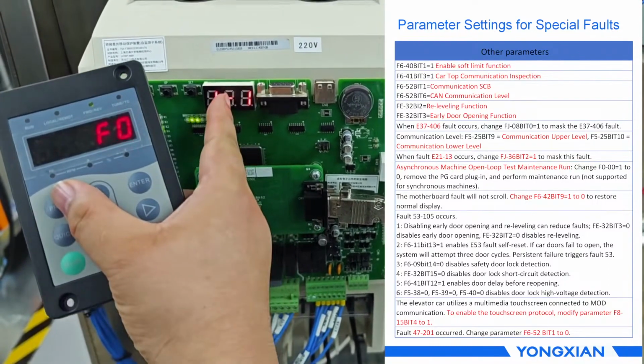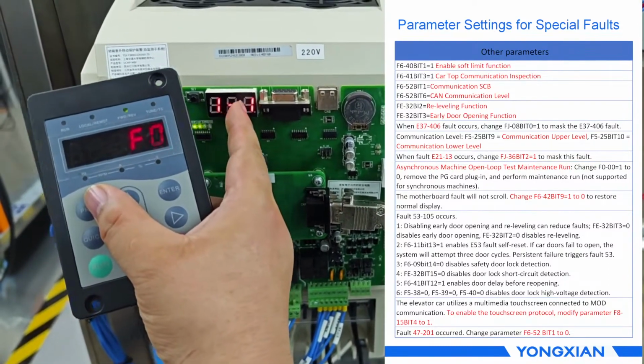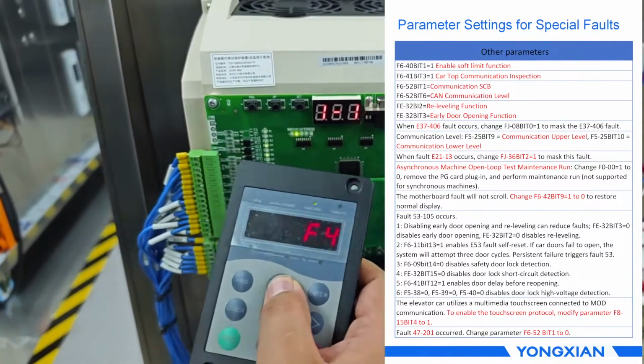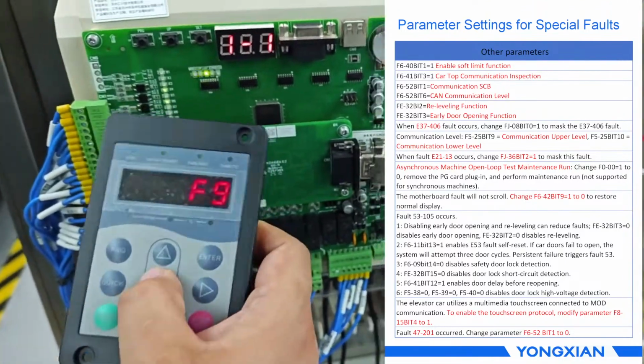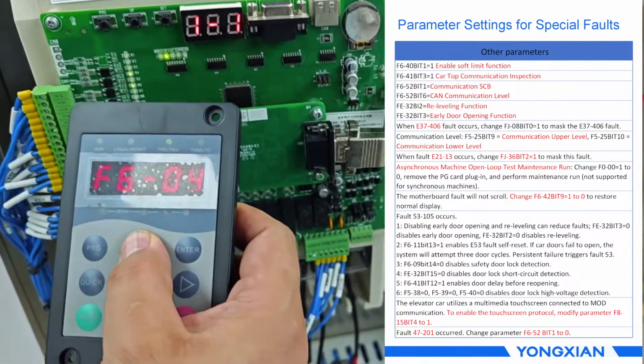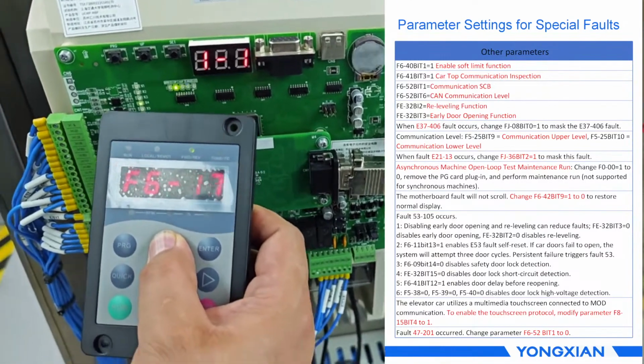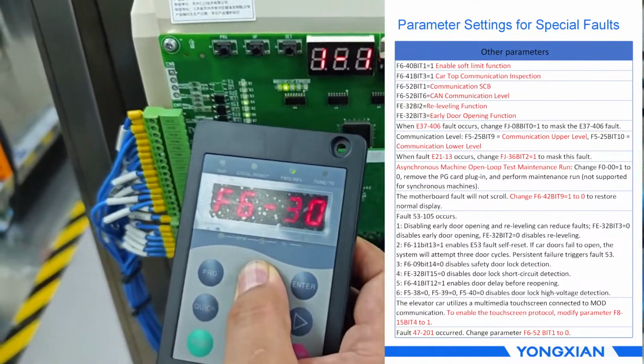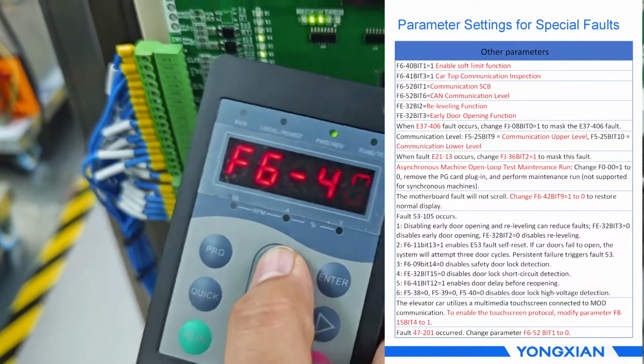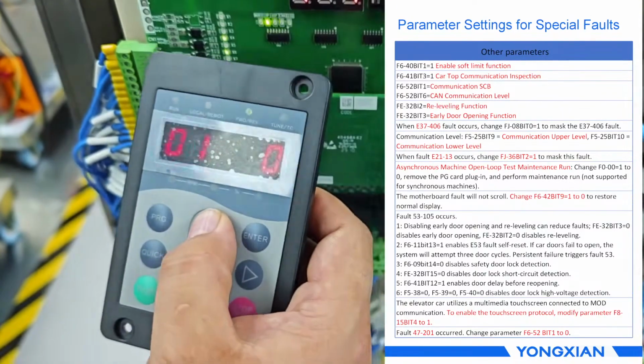如果我们的主板上面不会滚动故障代码，可以进入我们的 F642。The motherboard fault will not scroll. Change F642 bit 9 equals 1 to 0 to restore normal display.